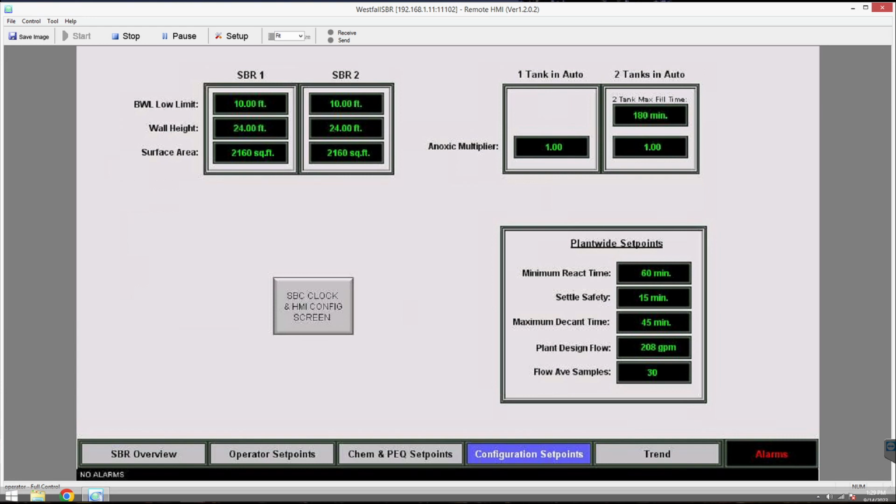Yeah, it's a lagged average filter. You get 30 samples in, but if you start up the SBR day one, it will take 30 minutes before it provides any output. No. It's not providing output immediately. It's just for the previous minute, and then for the previous 29 minutes, it's going to say, oh, well, my change in level was 0 before that. Right. Okay. It just looks at the most recent 30 minutes, and then a minute later, it throws out the oldest reading, and it adds one new reading. Yeah. Okay.